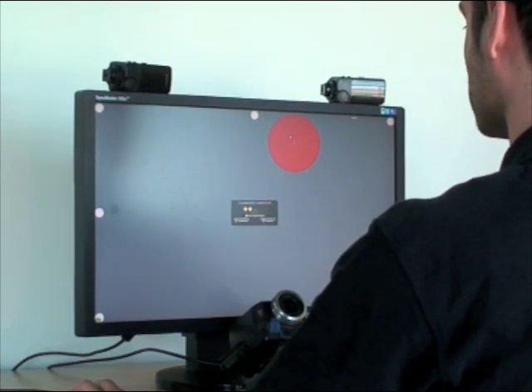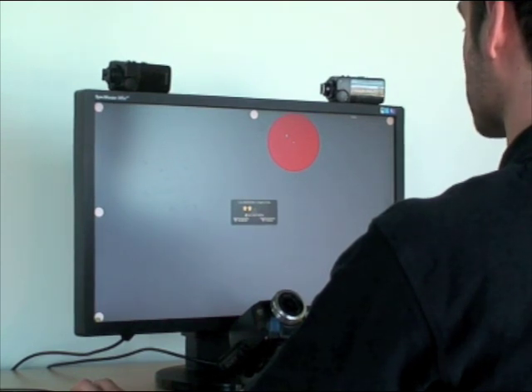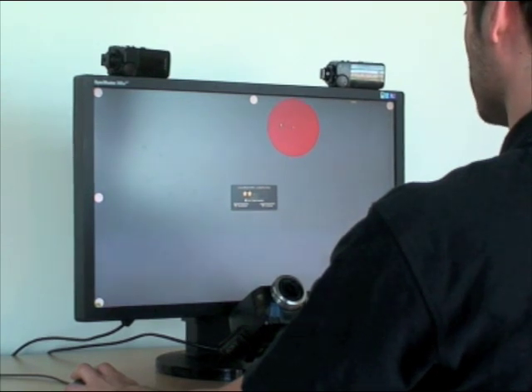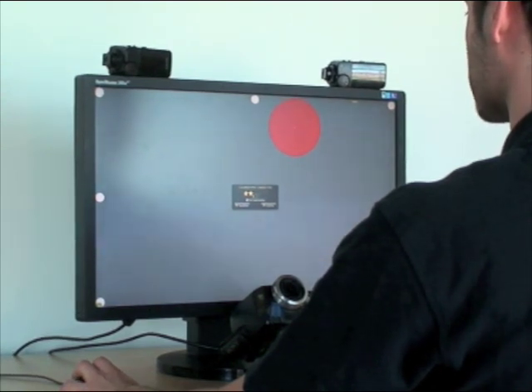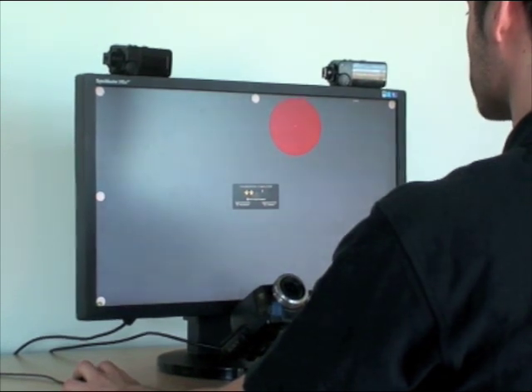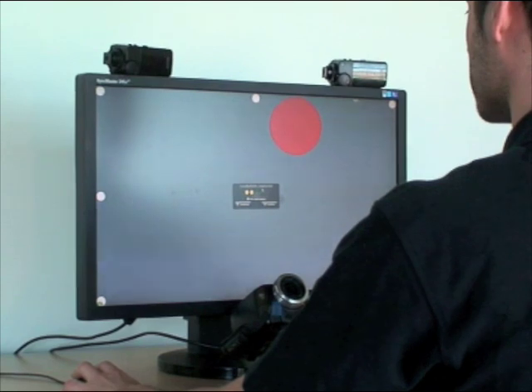For example, a big red circle represents a bad calibration point, while the others — where the point is enclosed tightly within the calibration target — represent good calibration results. In this case with a bad calibration point we only get a two-star score. When we get a lower rating we should recalibrate. If we get three or more stars we can try to use the eye tracker. When we finish the calibration there is a crosshair that will follow our eyes, so we can check how good the calibration is.